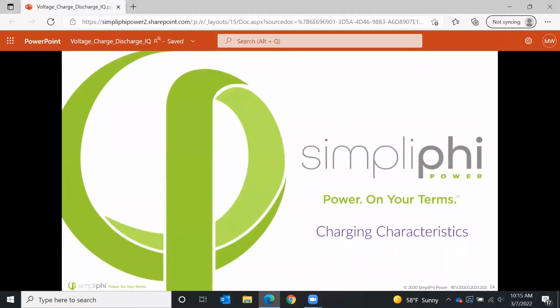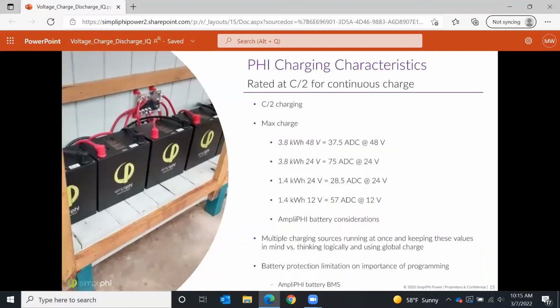Charging characteristics. So here's where we get into the fun stuff unique to today. I wanted to talk about mostly how to understand state of charge of a lithium iron phosphate battery. Our batteries are rated at C/2 for discharging and charging. So this means a 3.8 kilowatt hour capacity, divide that by 2, and that's the rate you can discharge or charge at, which is 1.9 kilowatts. You can do the same thing in terms of amperage. So in a 75 amp hour battery, divide 75 as the capacity by 2, and you've got your discharge rate or charge rate of 37.5 amps.